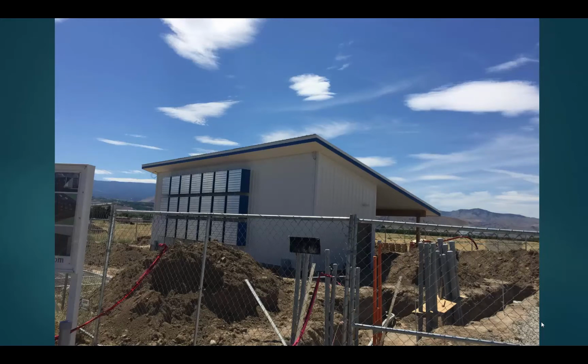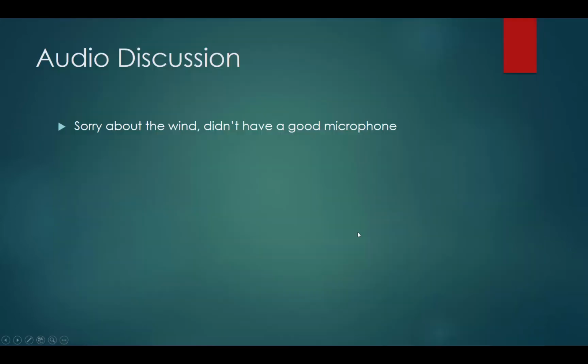And there she is. That's the construction, and we can see that the GigaPOD exhaust fans are all mounted directly. And here's the entry door, which they actually do plan to have card keyed access. And the overhang is used for sun protection and also protection from snow and the elements, because this is where they're having their evaporative cooling system. So all the inflow of air is coming this way. And if you look, basically this area right here is pointing west, so the winds coming in are going to be directly flowing into the input, which is really good design.